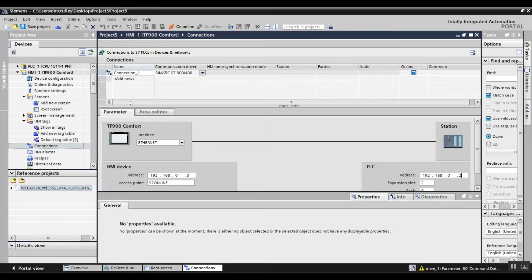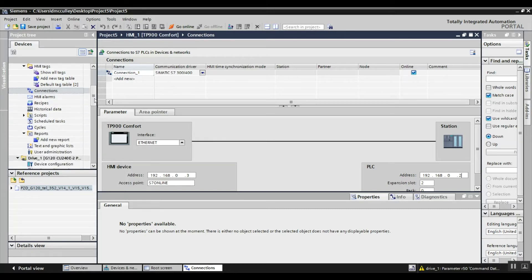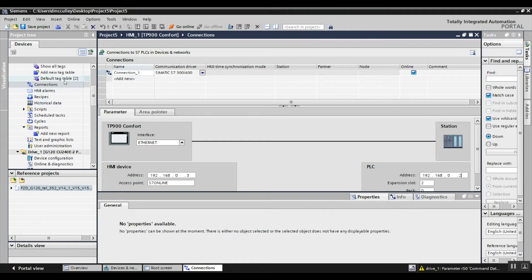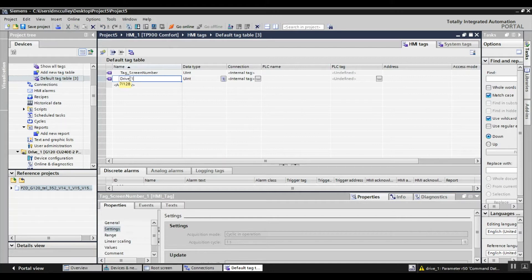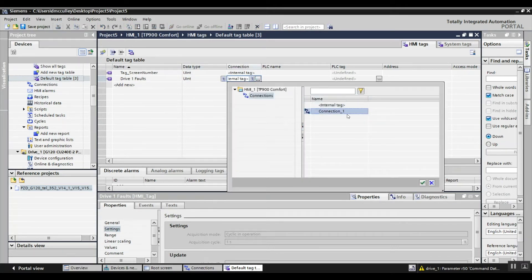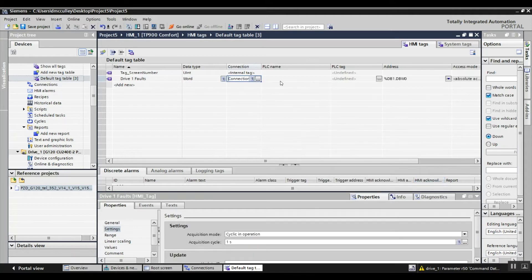Next I'm going to create tags for my faulted alarm. Drive one faults is going to have a connection of the one I just created, so connection 1. The data block address here pertains to the parameter number in the drive for the faults, so that's parameter 947 — db947.dbw0.